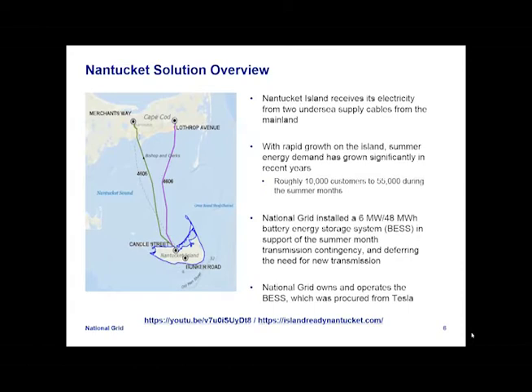The two cables that currently come into the island come into the Candle Street substation. If we were to install a third cable, there's actually no room in that substation for it. Based on contingency requirements, we'd also want to keep the third cable away from the existing two cables, which means it would have to come around the island into the Bunker Road substation, which is on the more southern tip, roughly near the middle of the island.